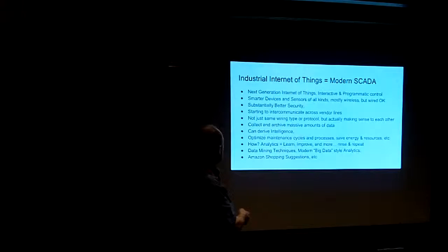So from that data you can then derive intelligence, which lets you detect where that pump is pumping against a closed valve. Do we really need to have the pump running right now? Should the valve be closed? Two good questions. Should we have a VFD on that pump motor? Is it going to save the price of the VFD in a short enough period of time? Those are the kinds of things this allows.